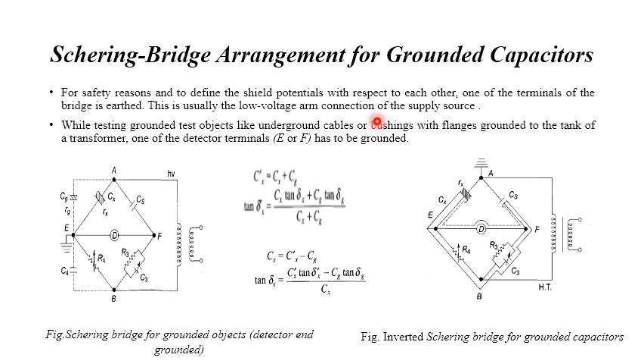ratio for the measurement. While testing grounded test objects like underground cables or bushings with the flange grounded to the tank of the transformer, one of the detectors, that is E or F, has to be grounded. So which is shown here, this is the one and this is the other one. These two are the bridges which are adopted for the measurement.